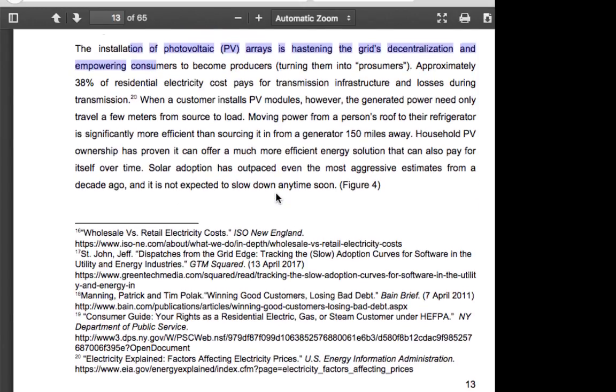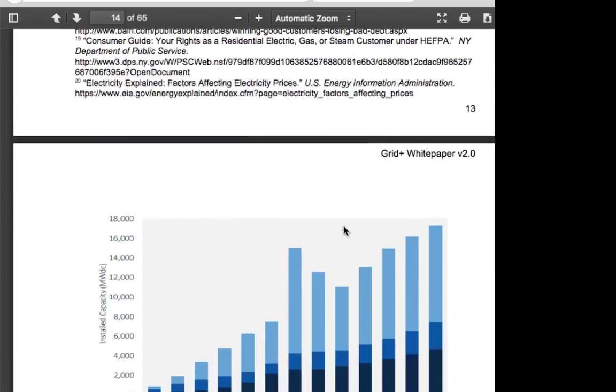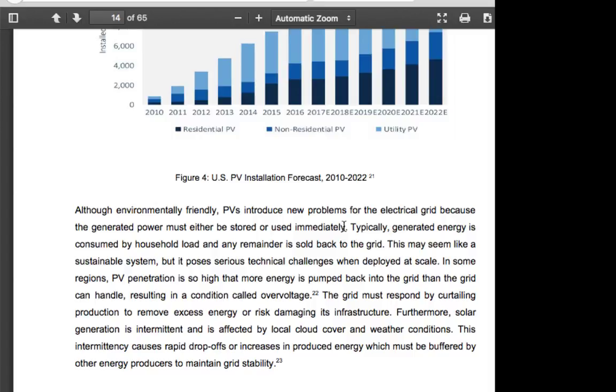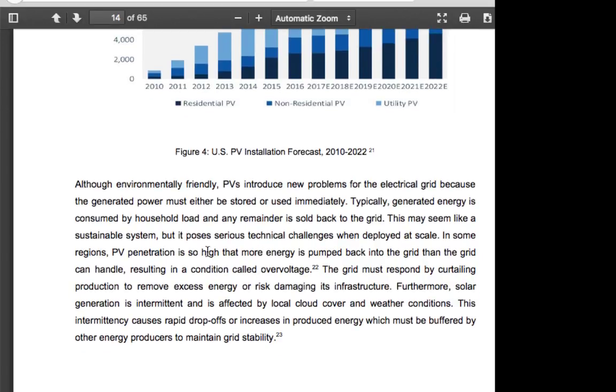In some cases, when you deploy photovoltaics, another challenge is that the grid actually needs to be upgraded, because the distribution lines aren't rated to carry large amounts of distributed energy. I've seen this result in what's called distribution upgrades, where they need to change the size of conductors or cables to allow power to be fed back into the grid. That can actually generate more costs. It sounds counterintuitive, but it does happen, and that's one of the challenges here.